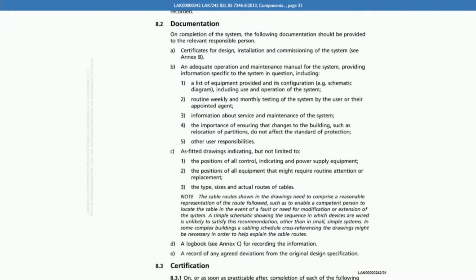And then at B, we can see an adequate operation and maintenance manual for the system, providing information specific to the system in question, including a list of equipment provided and its configuration, routine weekly and monthly testing of the system by the user, information about service and maintenance of the system, etc. C is as-fitted drawings, indicating but not limited to the positions of all control, indicating and power supply equipment, positions of all equipment that might require routine attention or replacement, the types, sizes and actual routes of the cables. And then D is a logbook at the bottom of the page, and E is a record of any agreed deviations from the original design specification. Now, were you familiar with those requirements? Yes, and as far as I'm aware, they were all acted upon.